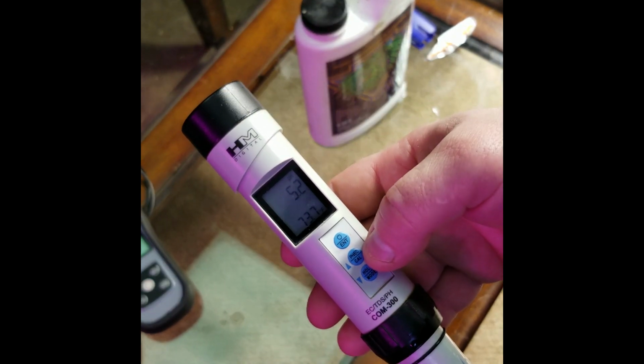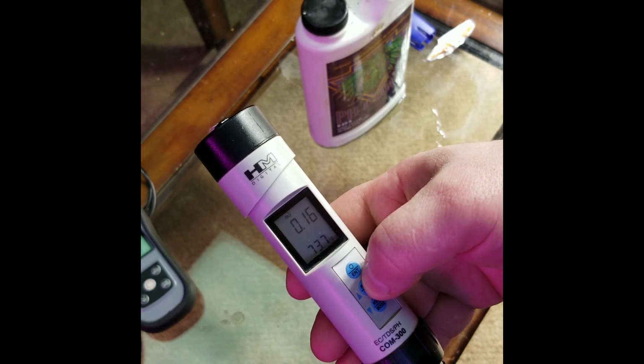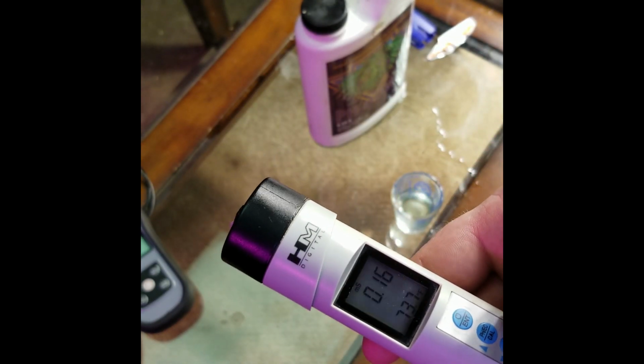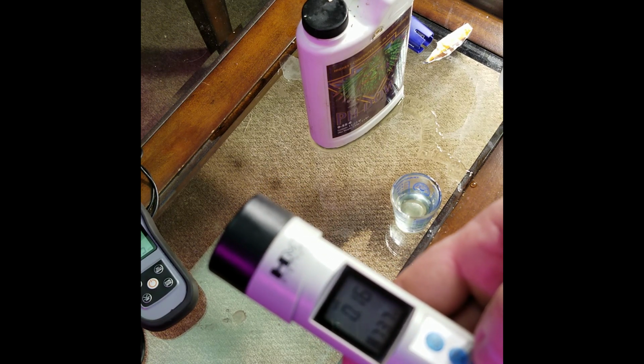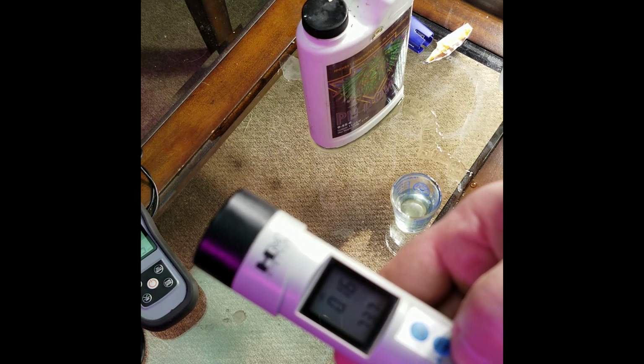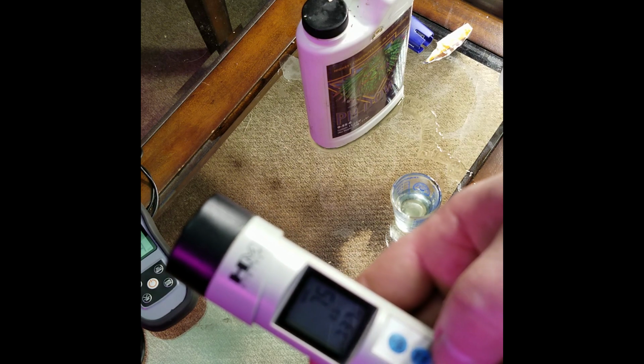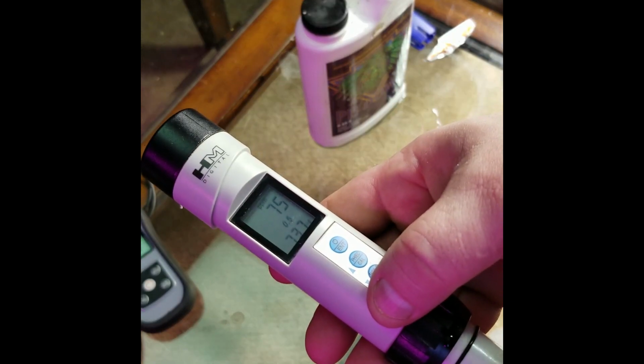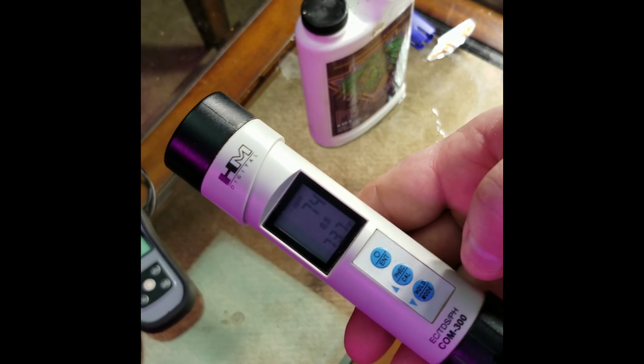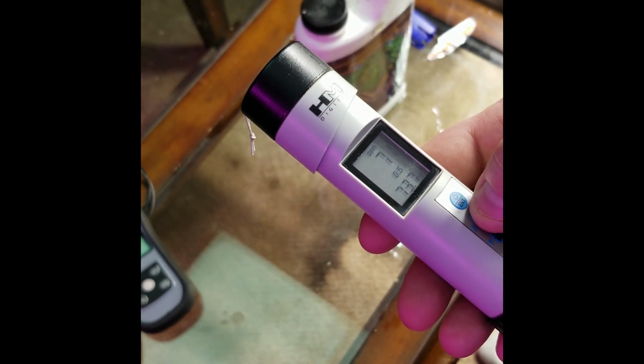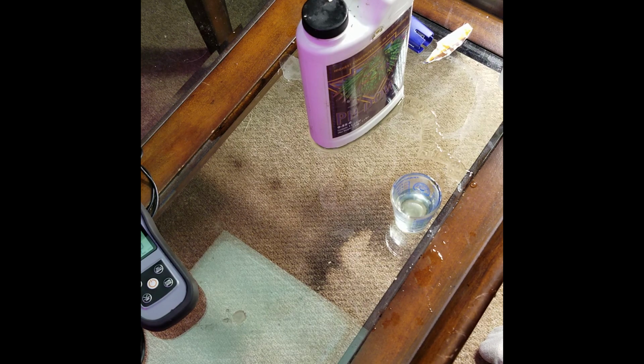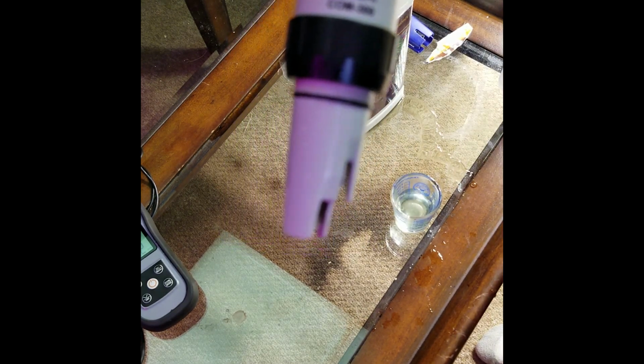So now, our HM COM300, we press the button in the middle to switch over to PPM. Now this one's set to MS. We need to switch that with the mode button. Sorry, we gotta hold the mode button. Now we're over to PPM and it says 0.5. So we're on the right scale. It says 71 ppm. We clean it all the way off. It should say 0.